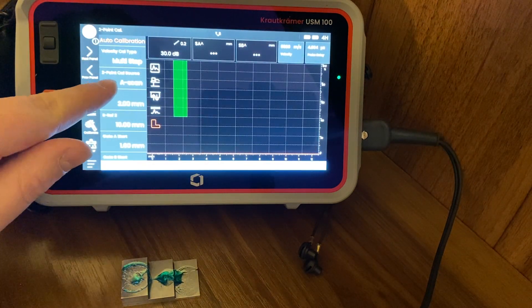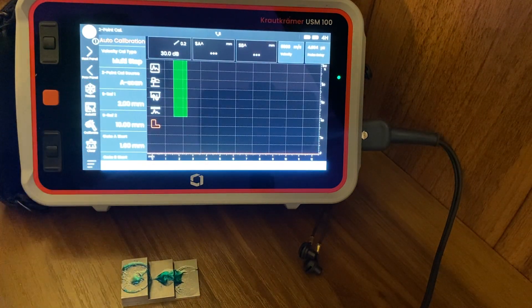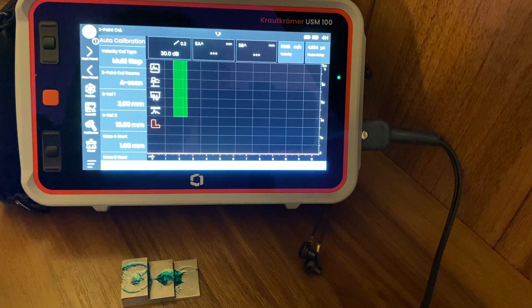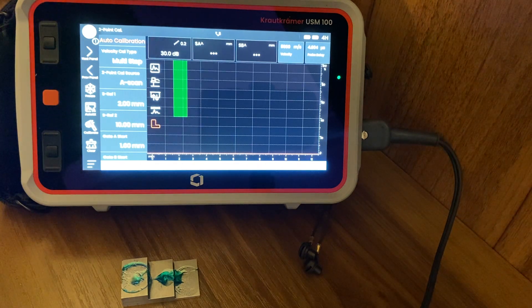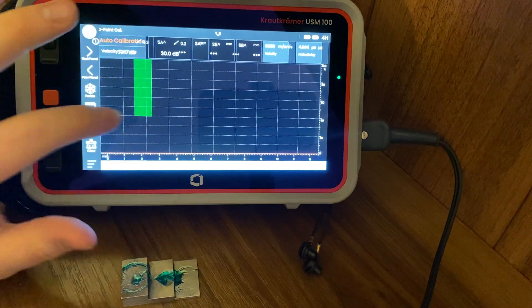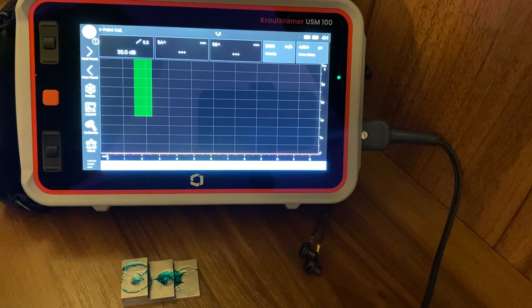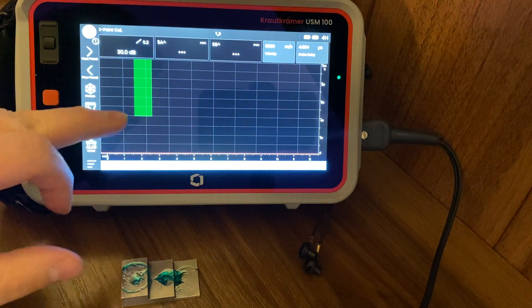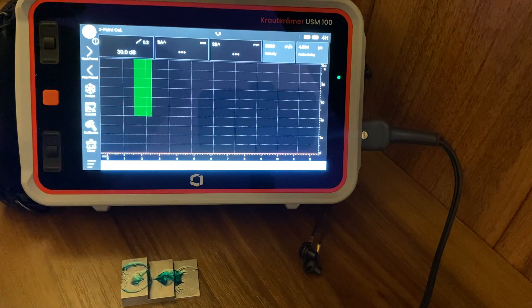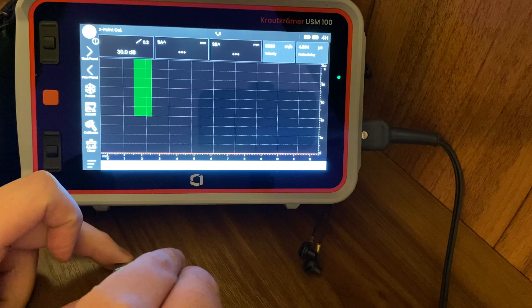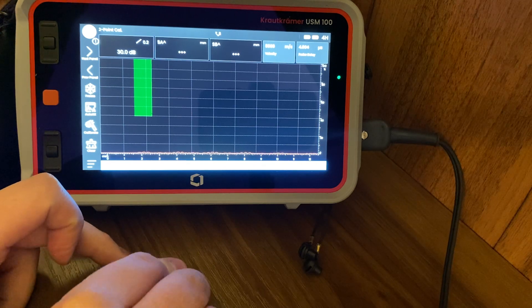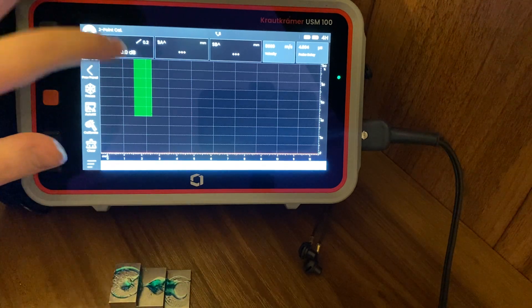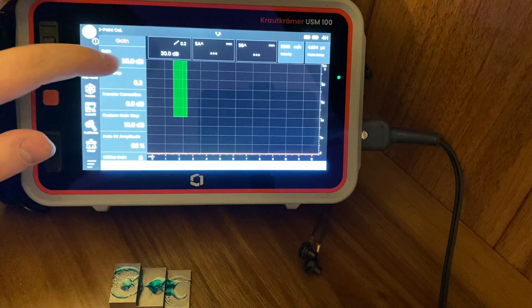You have the option of cal source A-scan. We could change that to envelope - I'm going to show you that in a different video. Today we're just going to get the quick standard setup. We could also change the data source from the peak or the flank of the A-scan, but for this purpose we're just going to set it up like this.